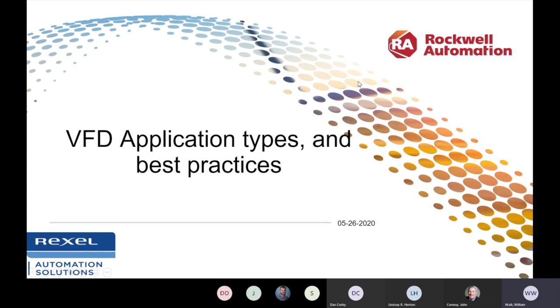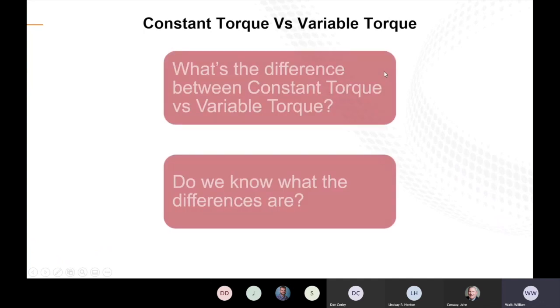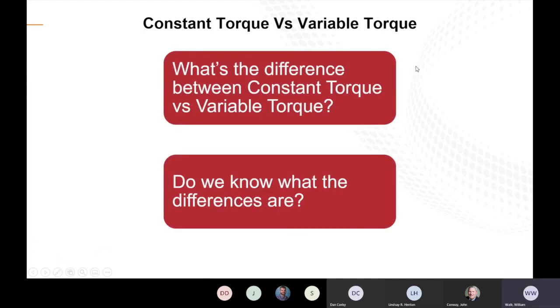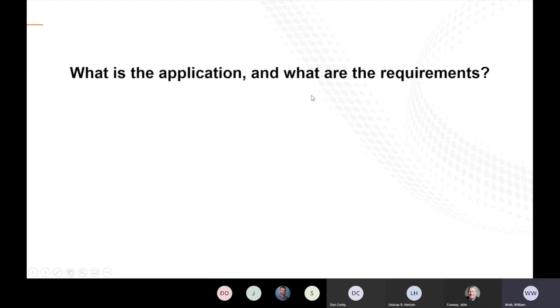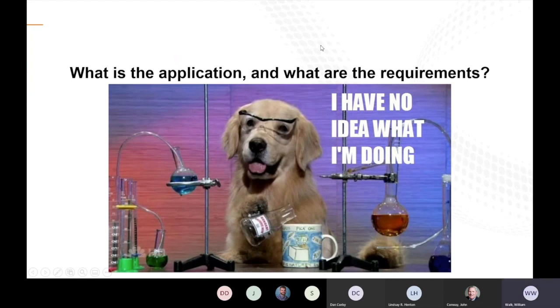So let's take a look at VFD application types and some best practices. We have 2 ways of sizing the VFDs: constant torque versus variable torque. What's the difference between constant torque and variable torque? And do we know what the differences are when it comes to sizing drives and speccing them out? Well, we have to ask a couple of questions first. What is the application that the drive is going to be controlling, and what are the requirements for this? If you're like me, you're having to look for answers online all the time.